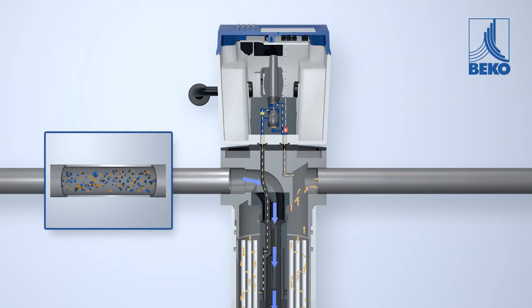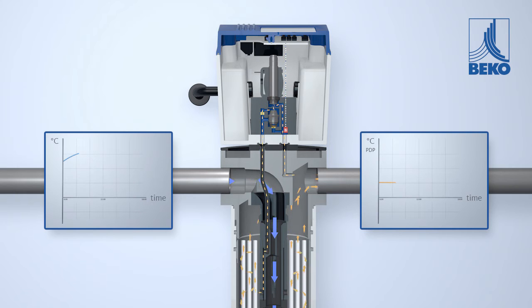Depending on the selected operating mode, either constant or dynamic, the set pressure dew point is either kept at a constant level or follows the compressed air temperature at the set difference value, regardless of fluctuating conditions on the dryer supply side.